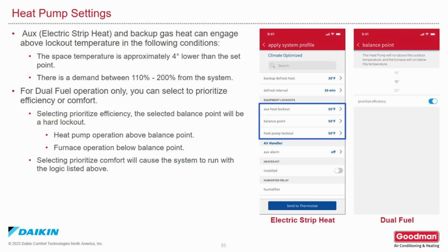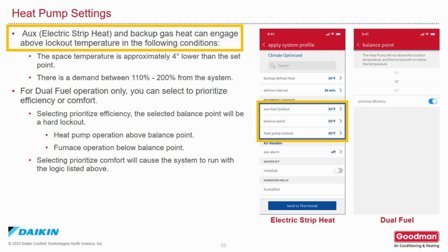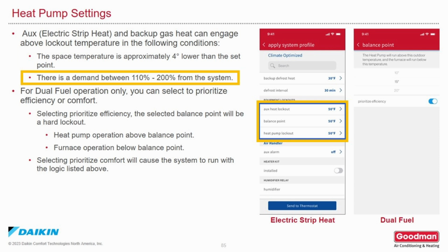As for the heat pump settings, auxiliary heat, whether it is electric heat strips or your backup gas heat, can be energized above lockout temperature if the following conditions are met. The space temperature is approximately 4 degrees Fahrenheit lower than the set point. There is a demand between 110% and 200% of the system.